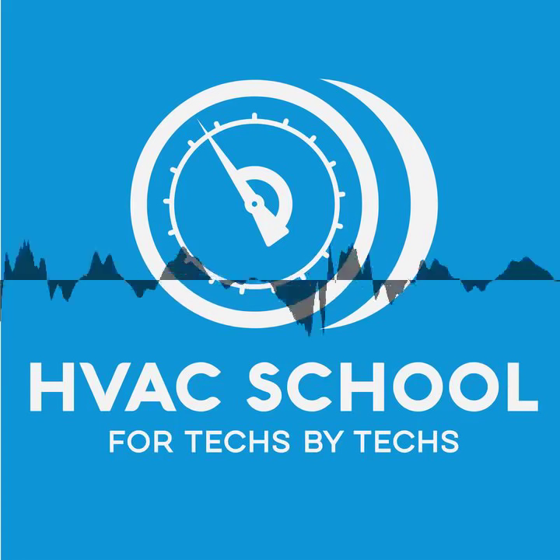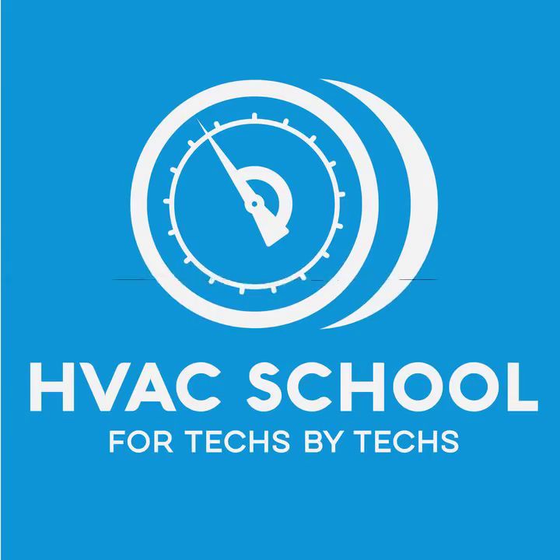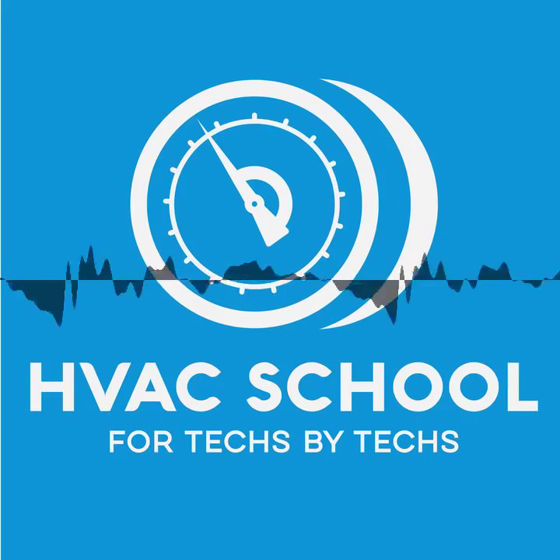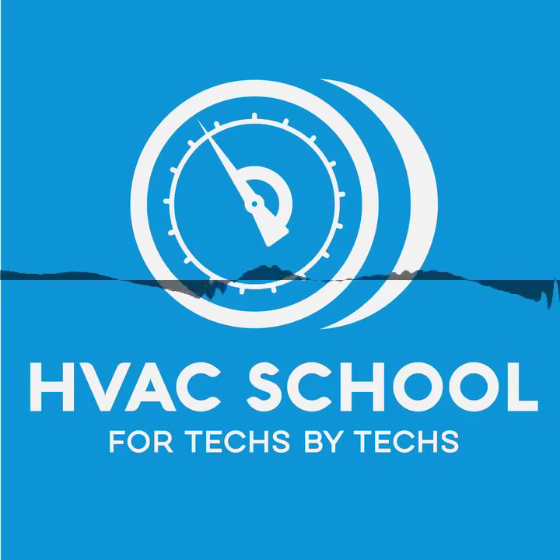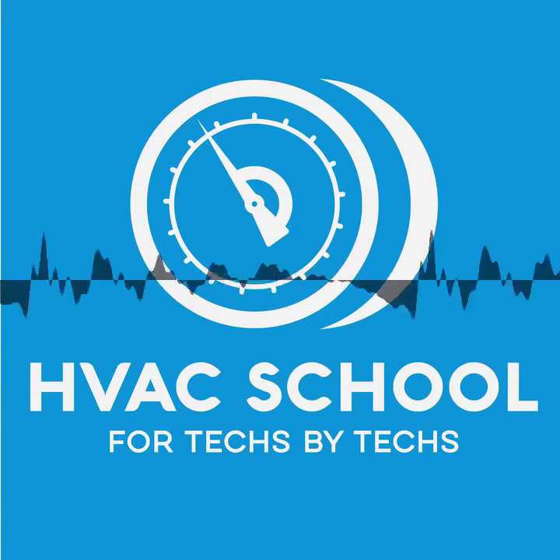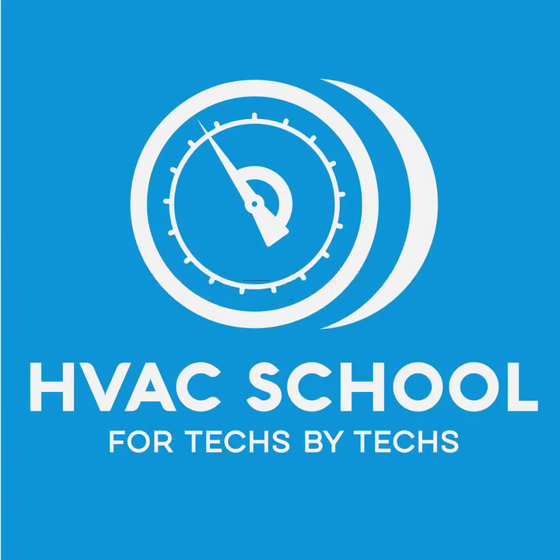As long as that evaporator coil is hitting dew point, we're going to pull moisture out of that air, and that affects the delta T quite significantly. So you can't just say, I should have a 20-degree delta T. That delta T can range anywhere from 14 degrees in some extreme cases, high airflow, all the way up to cases where your target could be a 24-degree delta T. That would be a case where you have low relative humidity air, so low enthalpy from moisture in the air, and then lower airflow. So you're going to see this range.